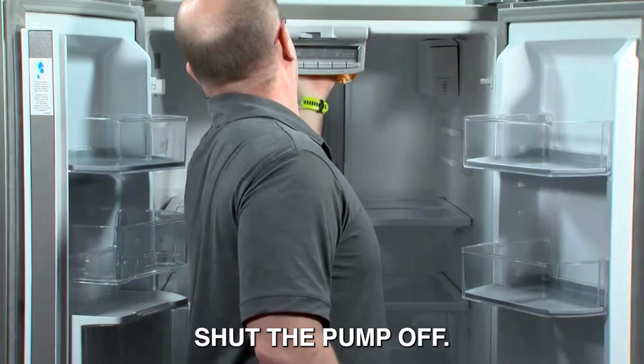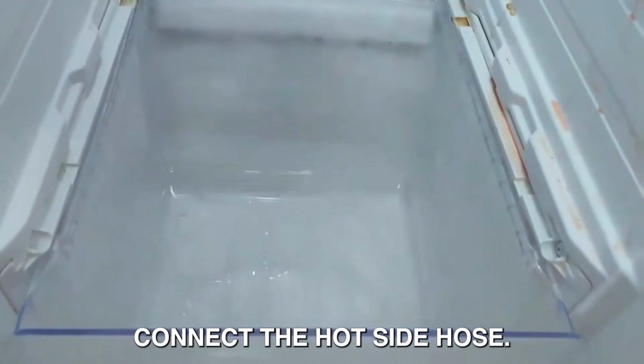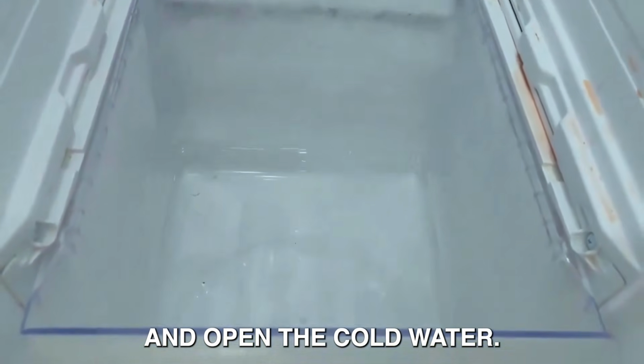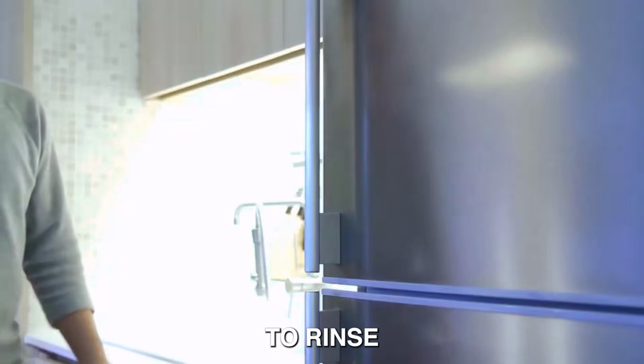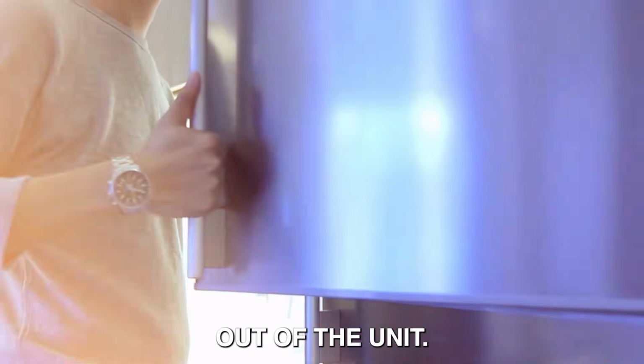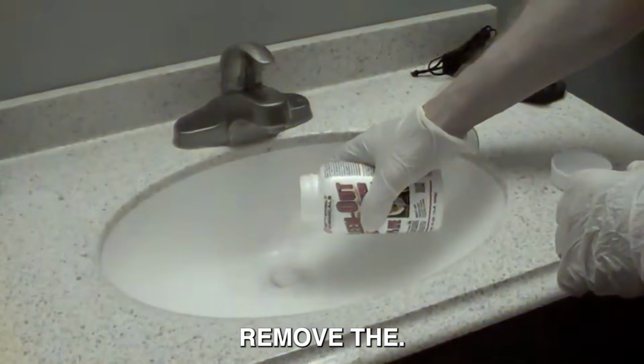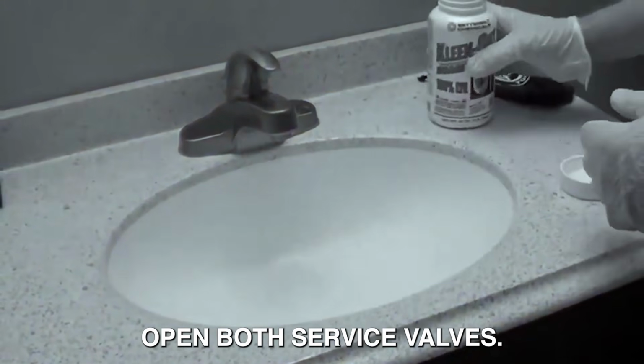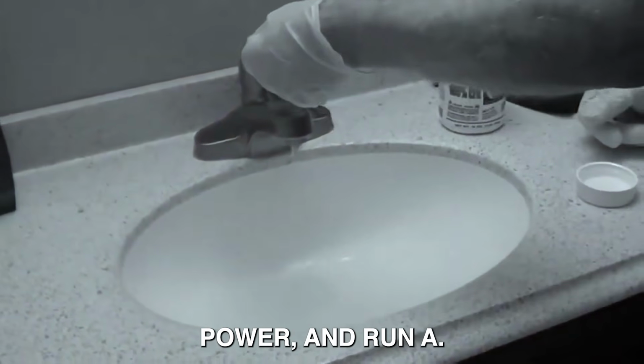Shut the pump off. Close the cold purge port, connect the hot side hose to a drain, and open the cold water inlet for 2 full minutes to rinse every trace of acid out of the unit. Close the purge ports, remove the hoses, open both service valves, restore gas and power, and run a hot tap until the temperature holds steady.